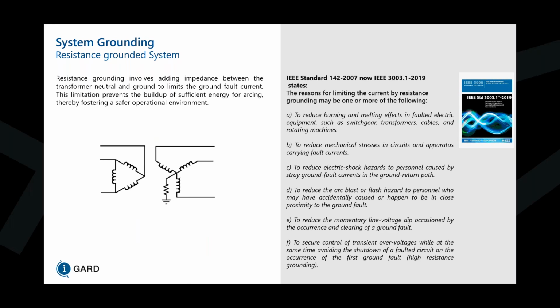Now in the IEEE standards, the reasons for limiting the current by resistance grounding may be one or more of the following. It's mostly to reduce the electrical and mechanical stresses from high levels of fault current, reducing electrical shock hazards, and to reduce the probability of arc blast or flash hazards to personnel, as well as equipment, and reducing the momentary line voltage dip occasioned by the occurrence and clearing of a ground fault. We're also trying to control the transient overvoltage by sizing this resistor in accordance to the charging current of the system. And in doing so, this type of resistance grounded system is much safer than an ungrounded system, which could experience transients in its ground return path.